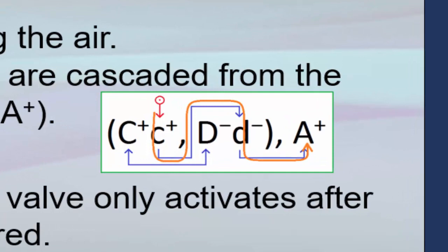So we can say that C has fully extended, okay, and then C plus, the limit valve C plus, becomes passing. It becomes open. Air comes out of it, and then it supplies limit D minus. When it is active, it becomes passing. Air goes through it, and then the signal can say, okay, we're done. These two actions are done happening, go on.